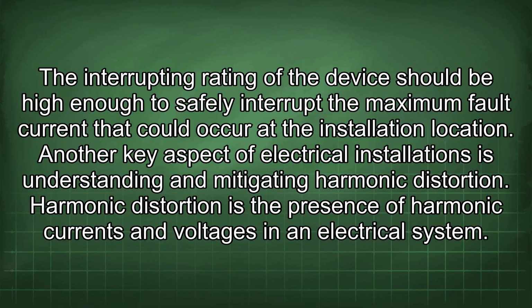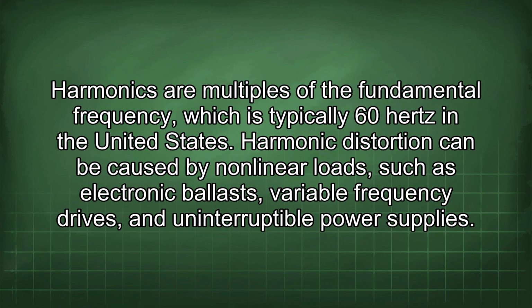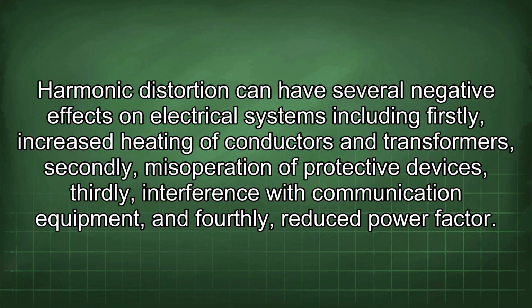Another key aspect of electrical installations is understanding and mitigating harmonic distortion. Harmonic distortion is the presence of harmonic currents and voltages in an electrical system. Harmonics are multiples of the fundamental frequency, which is typically 60 Hz in the United States. Harmonic distortion can be caused by nonlinear loads, such as electronic ballasts, variable frequency drives, and uninterruptible power supplies. Harmonic distortion can have several negative effects on electrical systems, including firstly, increased heating of conductors and transformers.